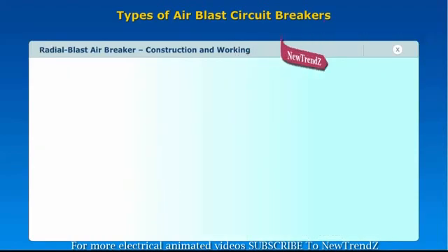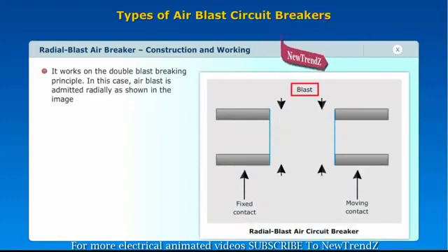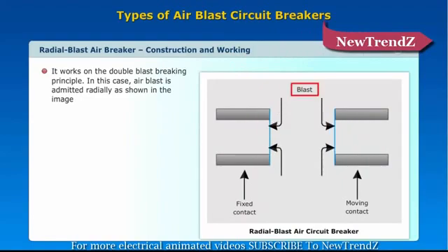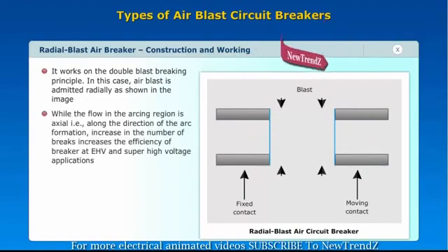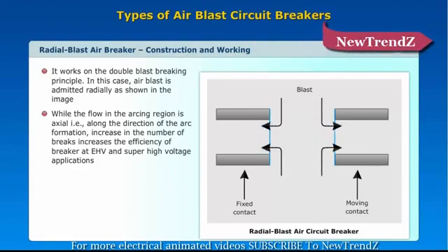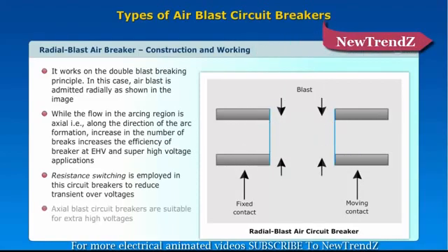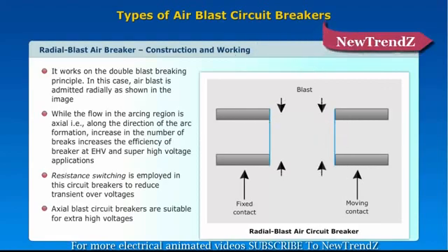Radial blast air breaker construction and working. It works on the double blast breaking principle. In this case, air blast is admitted radially as shown in the image, while the flow in the arcing region is axial — that is, along the direction of arc formation. Increasing the number of breaks increases the efficiency of the breaker at EHV and super high voltage applications. Resistance switching is employed in the circuit breakers to reduce transient overvoltages. Axial blast circuit breakers are suitable for extra high voltage applications.